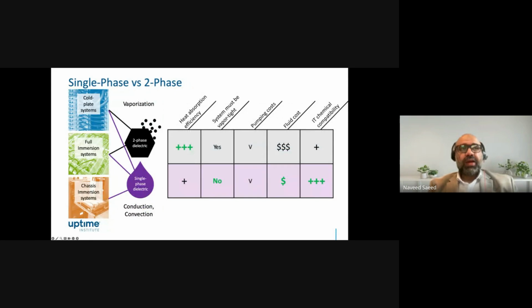There are certain advantages of using two-phase dielectric fluid and single-phase dielectric fluid. The heat absorption efficiency of two-phase dielectric fluid is considered to be higher than single-phase dielectric fluid. However, the two-phase dielectric fluid requires a vapor-tight system, so the vapor can condense back into the tank, while single-phase dielectric fluid doesn't require that. You definitely create a seal for dust and other equipment to be protected, but it doesn't need to be vapor-tight.